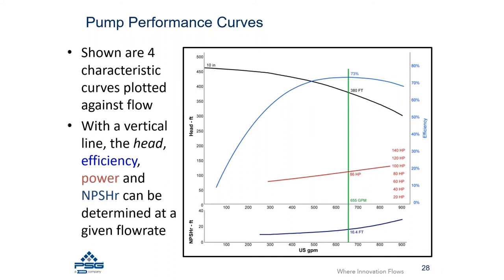Where the red line — representing horsepower — crosses the vertical line, it indicates this pump will require 86 horsepower. Down at the NPSH required curve, this pump would require 16.4 feet of suction head to ensure it is not cavitating. This is how you read a centrifugal pump performance curve. If you want to determine performance at a different flow rate, simply go to that flow rate and create another vertical line to read all the curve characteristics.